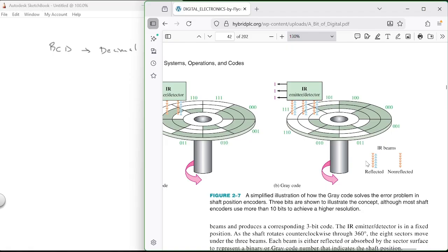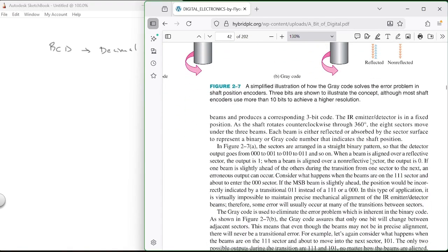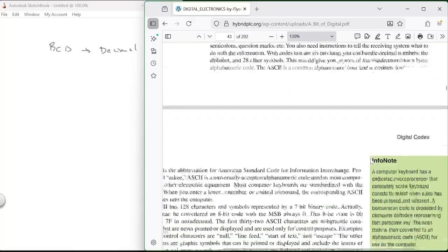Incremental encoders are advised. What's wrong with the incremental encoder? You have to go 1 time around to find your home position, because there's a bit that says I'm home, and then it's just on and off, on and off, on and off the rest of the way around. But if you put a battery in an incremental encoder, now you save where you were at any point in time, and that's why almost all servo motors that have an incremental encoder on them have a battery in them. So now all you have to do is remember to replace the battery every 5 years. So you don't have to do this. But anyway, that's about it.